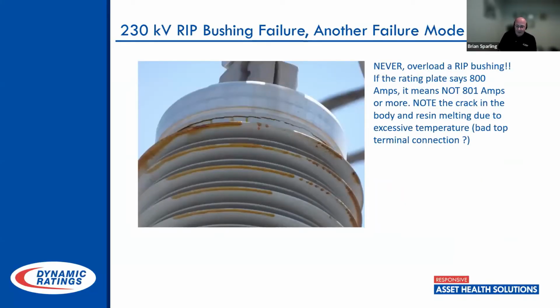There is another failure mode of RIP bushings, and it came to light when I was at an IEEE Transformers Committee meeting. One of the experts from one of the bushing manufacturers gave us a small tutorial on the application of RIP bushings. And I still remember his words. He said, you've got to understand one thing. If the rating plate on an RIP bushing says 800 amps max, that means 800 amps, not 801 or 802. It's 800 amps. That's all. There's no capacity for overloading RIP bushings, unlike with OIP bushings, where there's some tolerance level, I would say, for overloading.